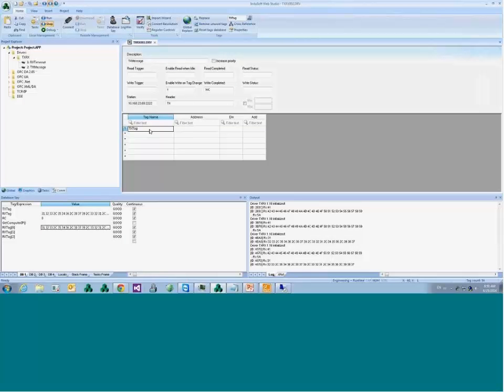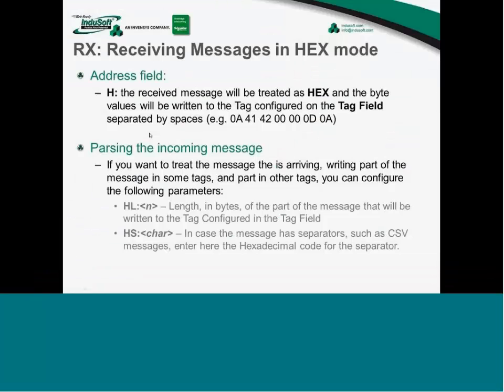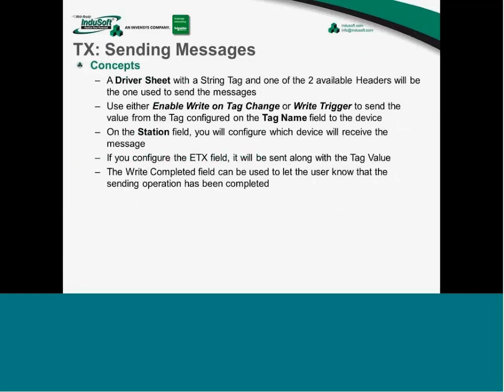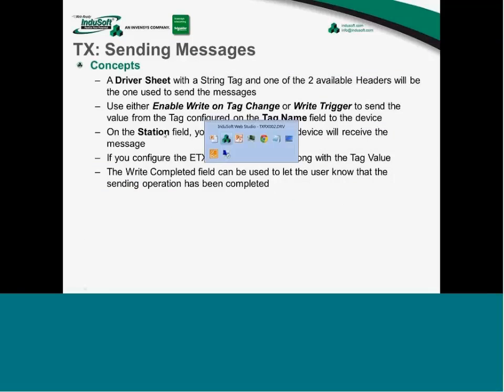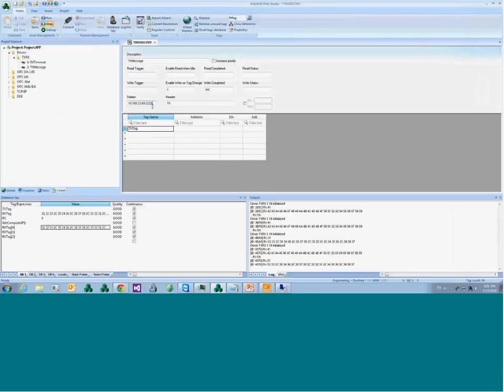Sending messages is even easier. You configure a TX worksheet with a string tag — whatever value is in that tag is sent to the device. You can trigger sending via 'Write on Tag Change' or a 'Write Trigger.' In the Station field, enter the IP address colon port number for the target device. For serial, leave station blank; for UDP going to a different address than configured in serial encapsulation, enter it here.